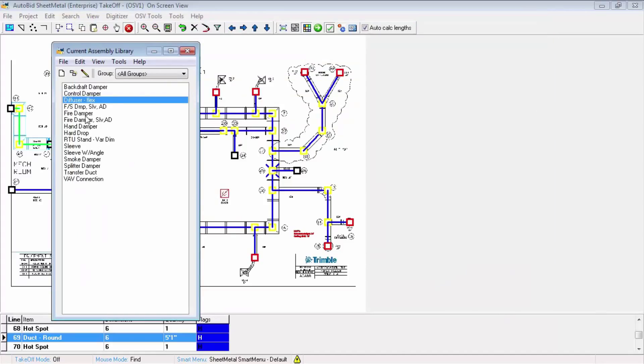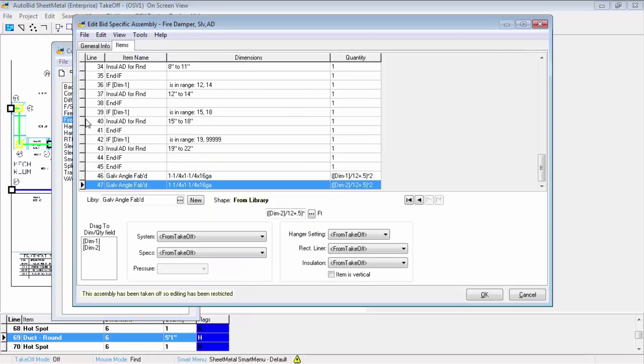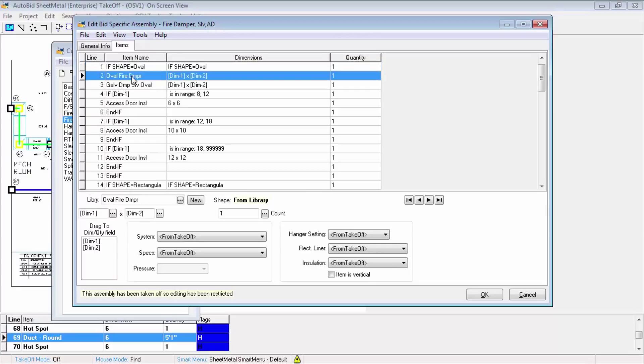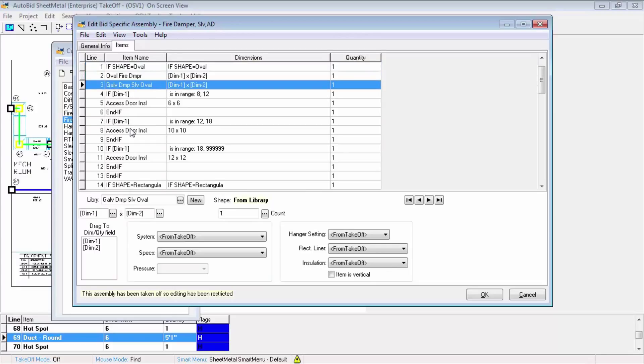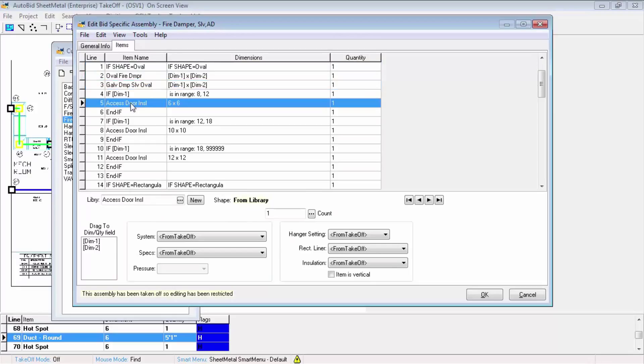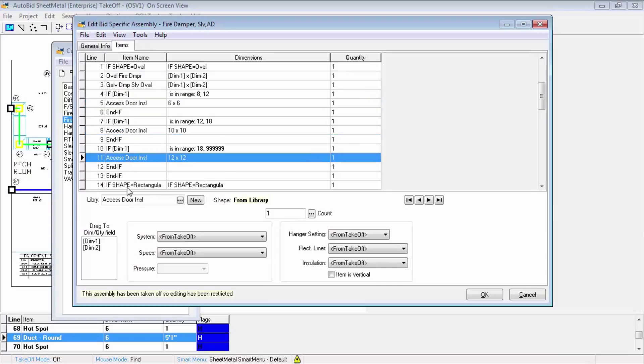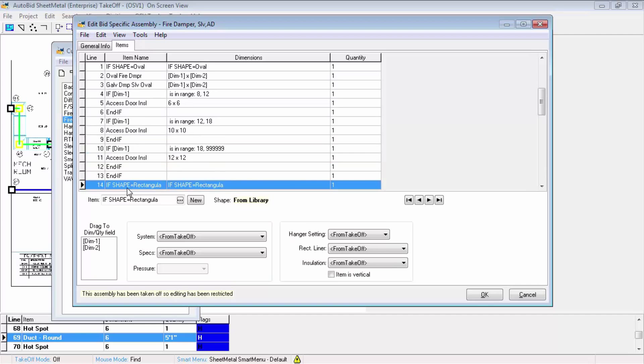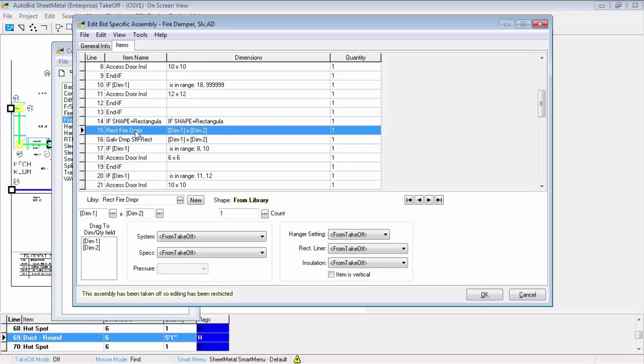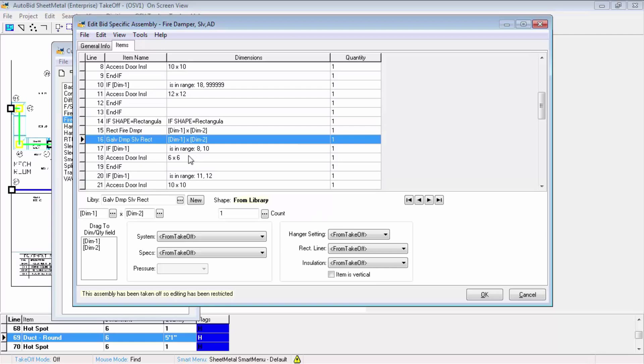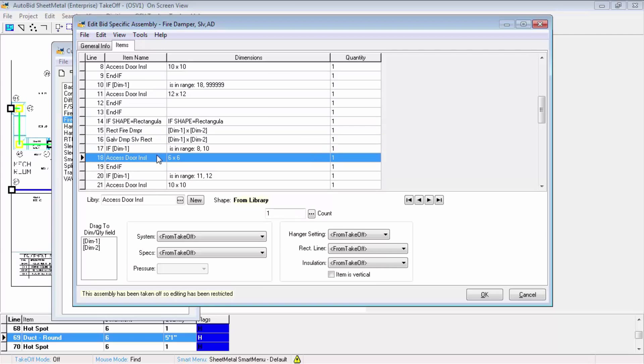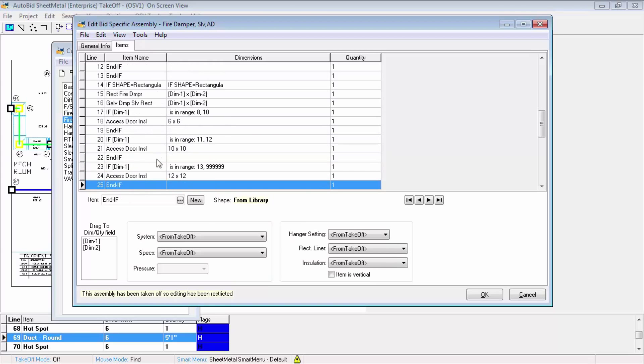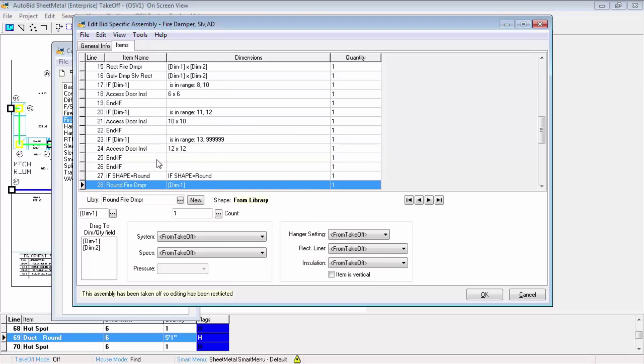We have some more complicated, sophisticated assemblies. Look at fire damper sleeve and access door insulation we had previously used in our takeoff. Starting at the top, you can see it starts out with an oval shape. We have comparison arguments in our assembly that if the shape was set to oval, gives us an oval fire damper and sleeve. We have a secondary comparison argument for dimensions. As the duct gets wider, the access door insulation automatically gets wider. This same assembly goes through the same comparisons for whether it's set to rectangular or round.